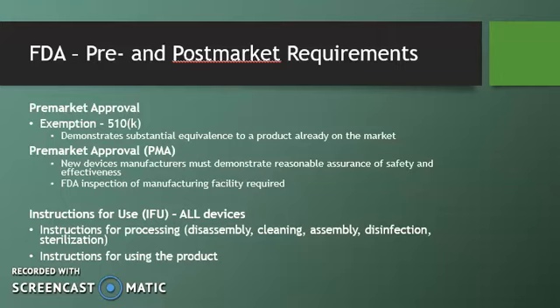Pre- and post-market requirements. Unless a device is listed as exempt from regulation, a 510K submission is required for Class 1 and 2 devices. Class 3 devices may require either a 510K or a pre-market approval, PMA. A 510K demonstrates substantial equivalence to a product already on the market, and a PMA requires new device manufacturers to demonstrate reasonable assurance of safety and effectiveness. FDA inspection of the manufacturing facility is required.